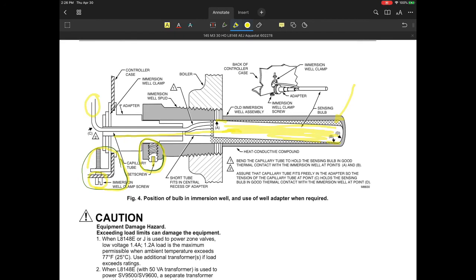This is very important. They're showing you in this picture how they want to see contact up on top. They want to see contact down here. They are trying to intentionally do that because they want to make sure that it's not floating in air. And if you put this heat conductive compound in there, it really reduces the necessity to try to make sure you have that Aquastat bent and moved up into this position in the way they're showing it here. This is a little bit challenging, but there again, be careful with this.